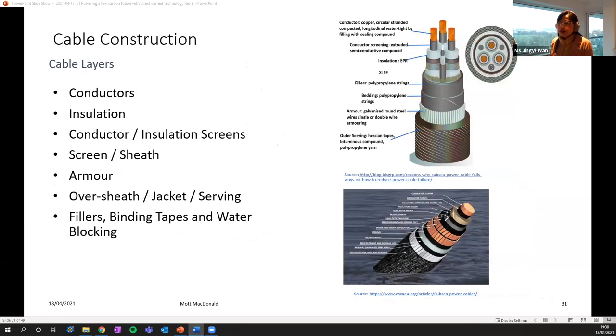Moving on to the components of a power cable. It consists of the following layers. Firstly, the conductor. It is normally copper, but sometimes aluminium. The choice of conductor material and design will affect system losses, cable handling, cable burial, vessel deadweight, and capital cost. Second, insulation. More detail will be discussed in the next topic about cable technology. Third, conductor and insulation screens. These are essential for smoothing the electric field, which would otherwise overstress the insulation.